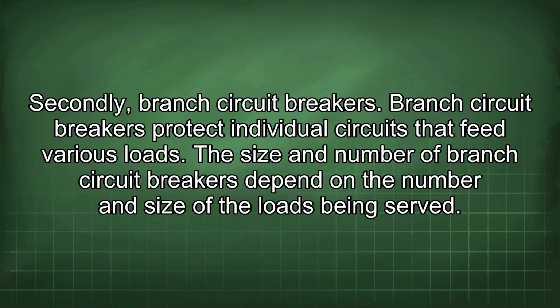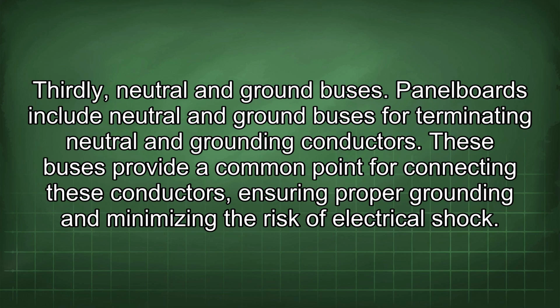The size and number of branch circuit breakers depend on the number and size of the loads being served. Thirdly, neutral and ground buses. Panelboards include neutral and ground buses for terminating neutral and grounding conductors. These buses provide a common point for connecting these conductors, ensuring proper grounding and minimizing the risk of electrical shock.